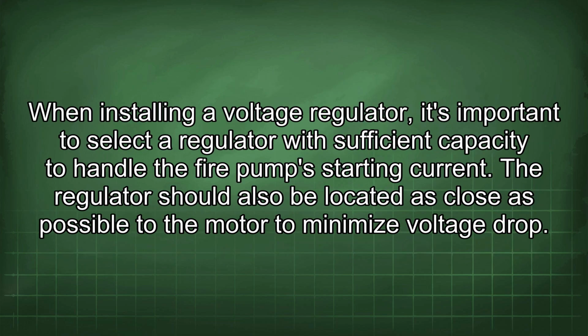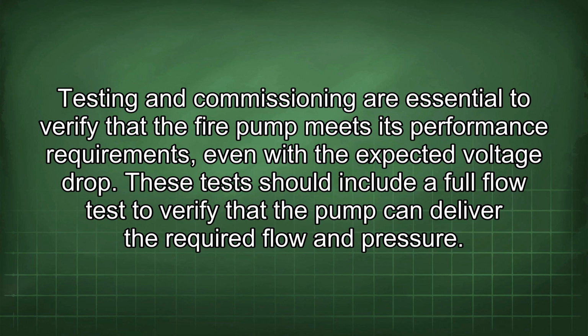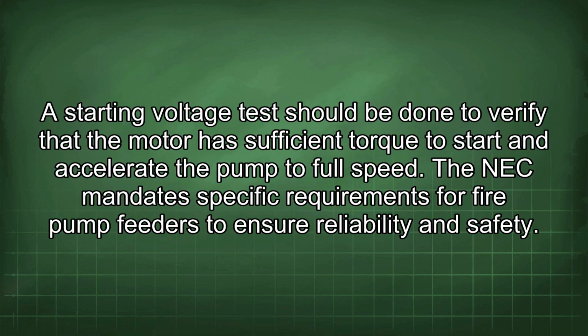When installing a voltage regulator, it's important to select a regulator with sufficient capacity to handle the fire pump starting current. The regulator should also be located as close as possible to the motor to minimize voltage drop. Testing and commissioning are essential to verify that the fire pump meets its performance requirements, even with the expected voltage drop. These tests should include a full flow test to verify that the pump can deliver the required flow and pressure. A starting voltage test should be done to verify that the motor has sufficient torque to start and accelerate the pump to full speed.